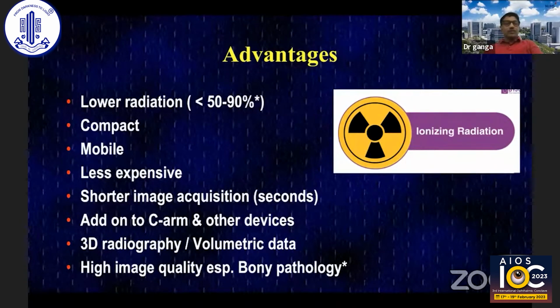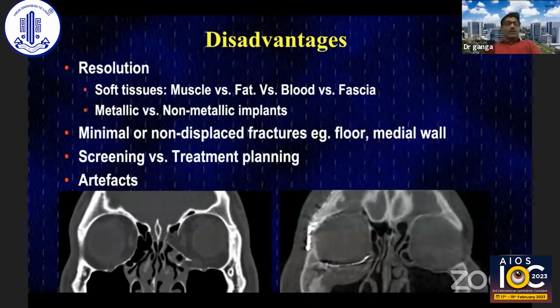The big advantage of using cone beam CT scan is that it has almost up to 90% less radiation than the conventional CT scan. Ionizing radiation is a bad word, and every time a CT versus MRI debate comes about, especially in patients with germline mutations and a few other conditions, we don't like ionizing radiation. These machines are very compact and very mobile. They're very inexpensive, so to speak, with short image acquisition times. In fact, patients walk in and walk out without any scheduled appointment, and it can be added on to any C-arm technology that we have. And when you're really looking at bony pathology, we can get whatever information we want. But there are a few limitations.